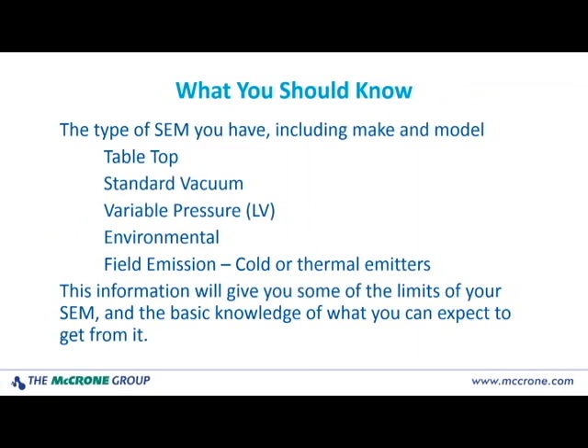So if you're starting out, what you want to find out is what type of SEM do you have? You want to know the make and model of that SEM. Is it a tabletop? You're going to have very limited parameters and controls if it's a tabletop SEM. You go to the standard type SEM, which operates in standard vacuum conditions — you're talking 10 to minus 5, 10 to minus 6 torr — you have a lot more controls available to you. You have what's called a variable pressure SEM or a low vacuum SEM. This is just an extension of the standard SEM. It allows you to look at samples that may not be fully conductive, where in the standard SEM you only have one option available. The sample either has to be conductive or you have to find some way to get around the sample charging.